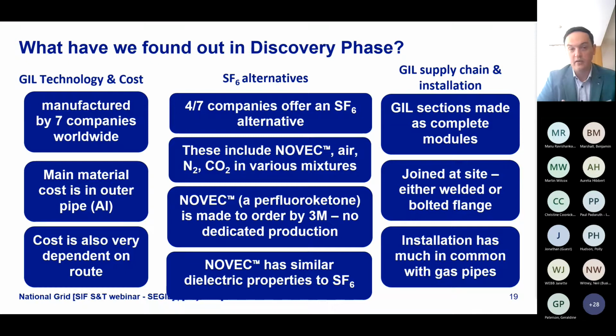There's proposed air, proposed nitrogen and CO2 in various mixtures. However, the problem with air, nitrogen and CO2 is that they have lower electrical strength than SF6, meaning the pipeline should be bigger to create enough clearance distance, meaning the pipe gets bigger, more material, more costs. See the point in the previous column.